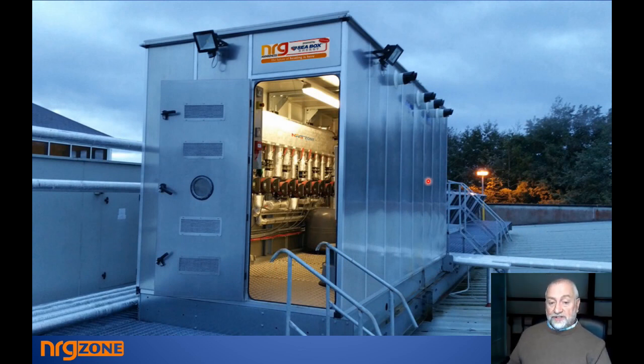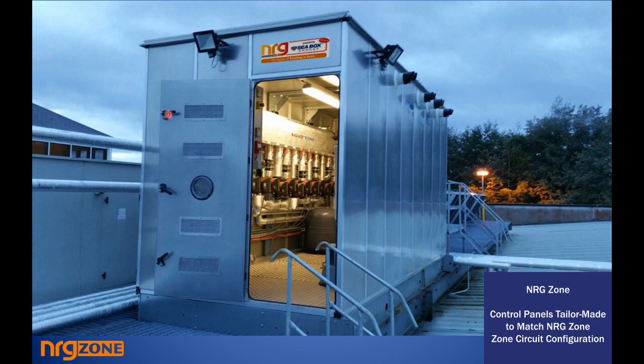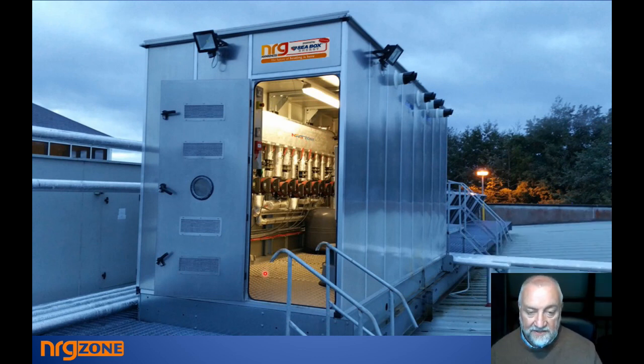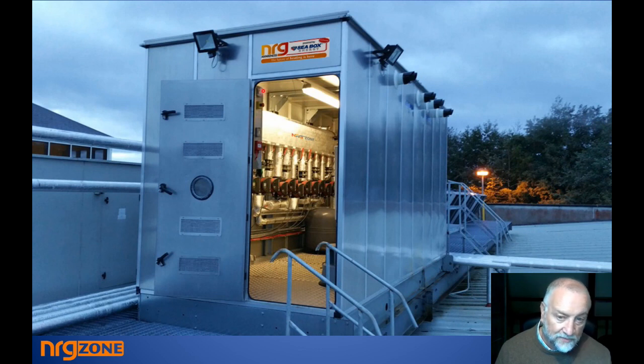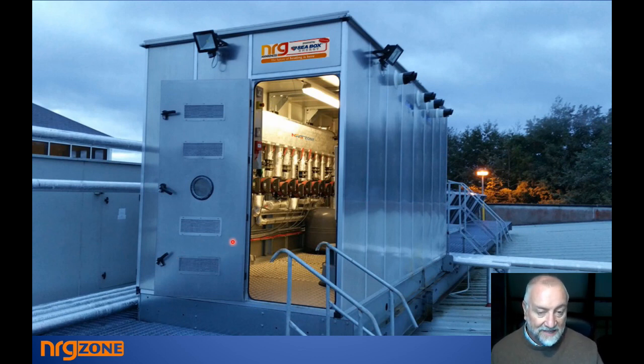So this is a very interesting job in a large supermarket. It was an air handling unit, so we made this containerized unit with 4 15 kilowatt boilers, wall hung boilers. They go into a large manifold, each with its own circuit down onto separate air handling units, and there were overdoor units and whatever. And then there was also hot water control inside the unit. And just round the corner here, you can see the side of here was our control panel. So this was just dropped onto the roof. The pipework was prepared in advance, and then it was a really rapid exchange. The system was completely connected in 2 or 3 days, in and out. So very fast. It's been there for years, never a callback, just working absolutely like a dream.